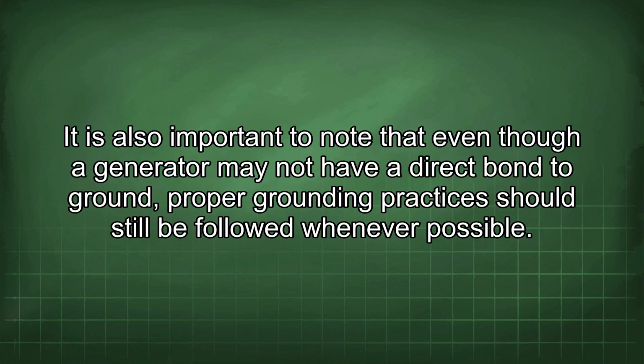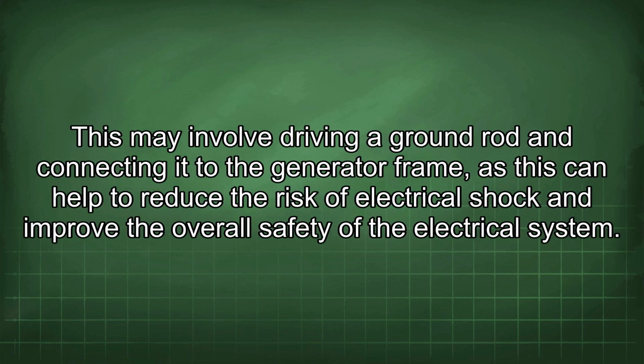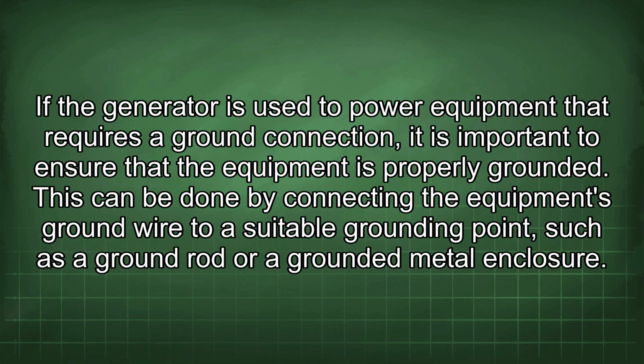It is also important to note that even though a generator may not have a direct bond to ground, proper grounding practices should still be followed whenever possible. This may involve driving a ground rod and connecting it to the generator frame, as this can help to reduce the risk of electrical shock and improve the overall safety of the electrical system. If the generator is used to power equipment that requires a ground connection, it is important to ensure that the equipment is properly grounded. This can be done by connecting the equipment's ground wire to a suitable grounding point, such as a ground rod or a grounded metal enclosure.